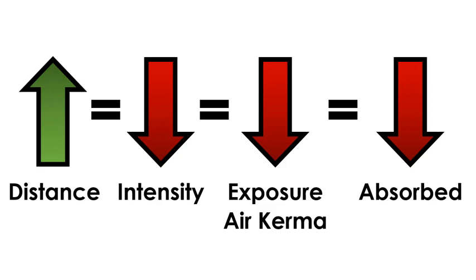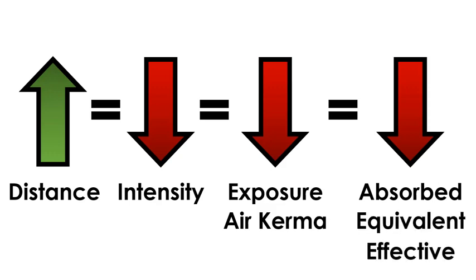We could also change the distance and the result is different. If we increase the distance between the person and the x-ray source, this is going to result in a decrease in the intensity of the x-ray beam according to the inverse square law, which then will result in a measurable decrease in the exposure and air kerma, and if those things are decreasing, the absorbed dose, the equivalent dose, and the effective dose also all decrease.